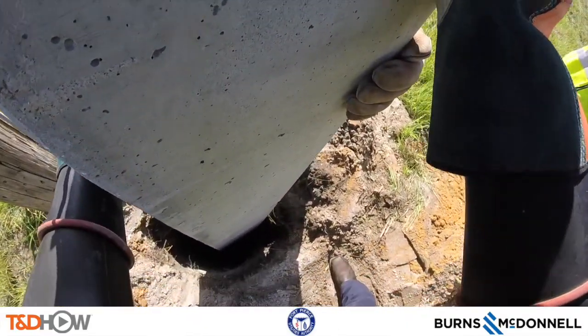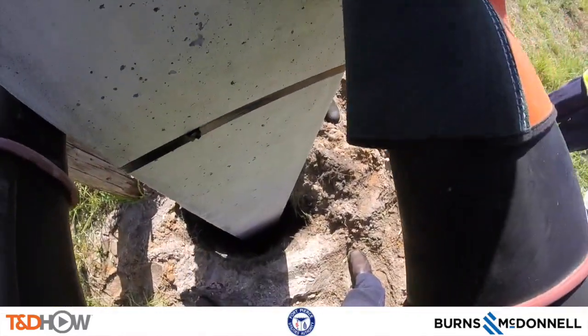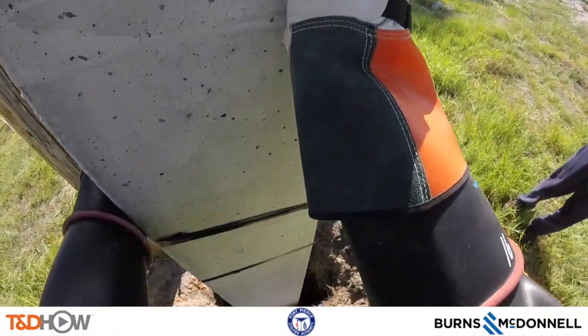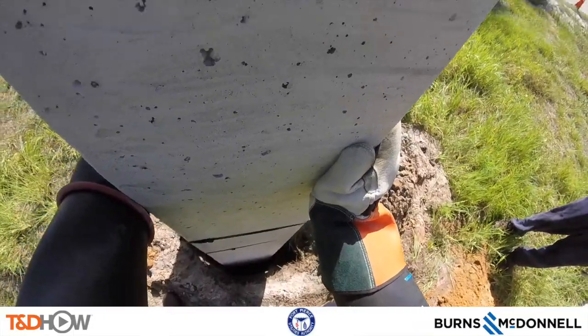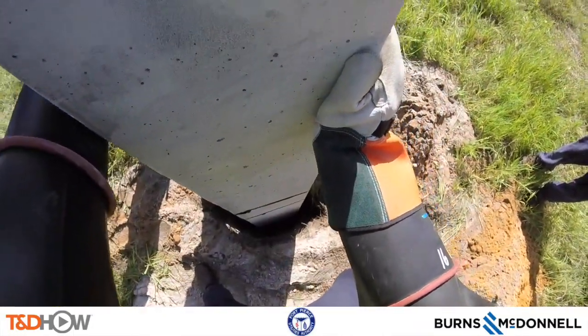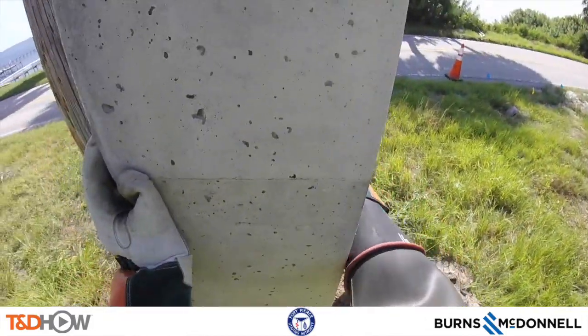Those tape marks tell them how far down to go in order to achieve the proper height above ground. They also have to make sure the cant is right — meaning the direction of the pole is correct regarding the openings at the top for cross arms and fuses. You can hear the crew confirm: 'Make sure the cant is right.